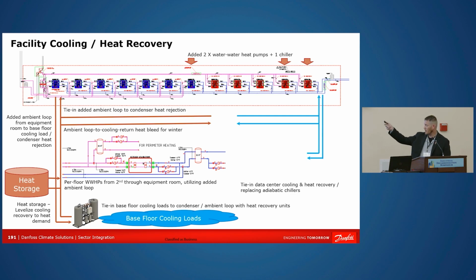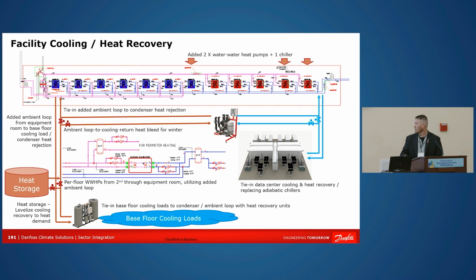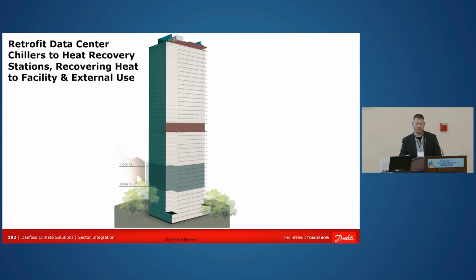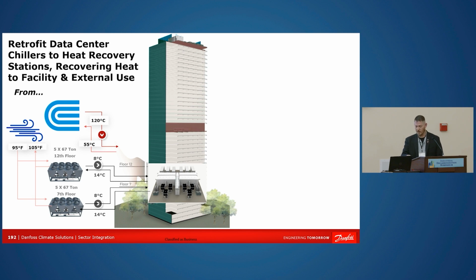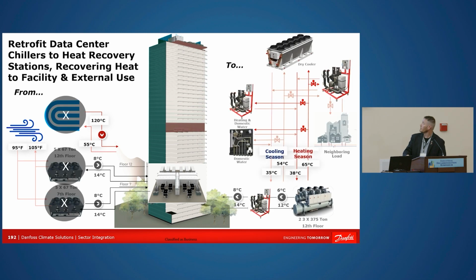And this goes on to the schematics and the P&ID of how we've come up with this solution and how we're working for it in the future. It also ties on for, if you take a look at the bottom left, heat storage, level cooling, recovery to heat, and the demand. So it ties in base floor cooling loads to the condenser ambient loop recovery units. Also ties in the data center cooling and heat recovery, replacing adiabatic chillers. Retrofit the data center chillers to heat recovery stations, recovering heat to facility and external use. And this is what we've come up with, the initial plan, and the solution is going to be coming up. For our solution to the dry coolers, heat recovery stations, heating domestic hot water, all the way down to a 375-ton 12th floor heat pump that goes back into the system. This will also incorporate neighboring loads and can help out with the neighboring loads.